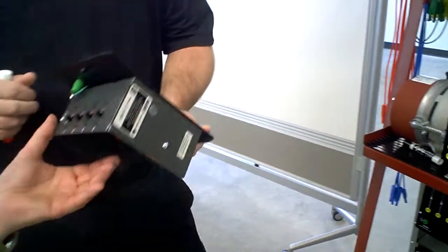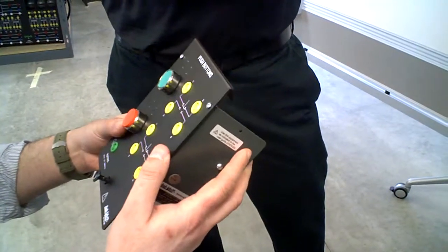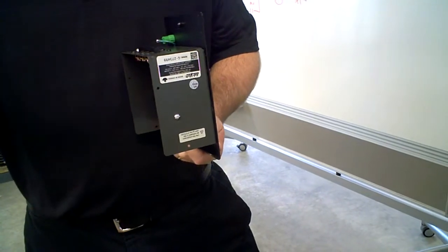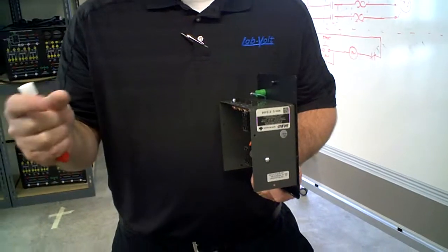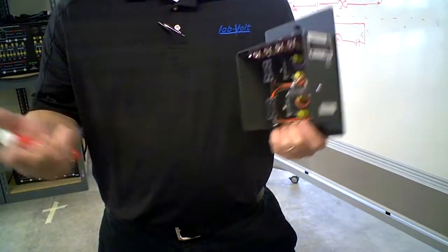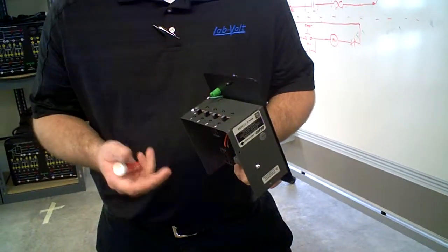Does the instructor's manual tell you what those are? There is a list in one of the books. I'm not sure which one. And then you put a resistor in there so if you short it, you're not burning anything out. Actually, one of them is shorted completely. So it shorts one of them out completely. One of them just adds resistance to it so that it won't have the holding current to be able to keep the motor starters energized. And then one of them is open. And then I don't know what the other one is. We can measure them in a little bit and see.